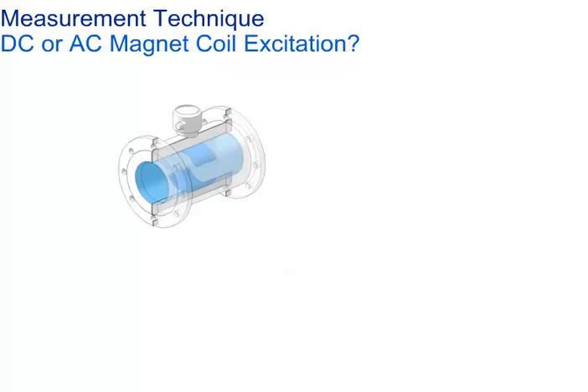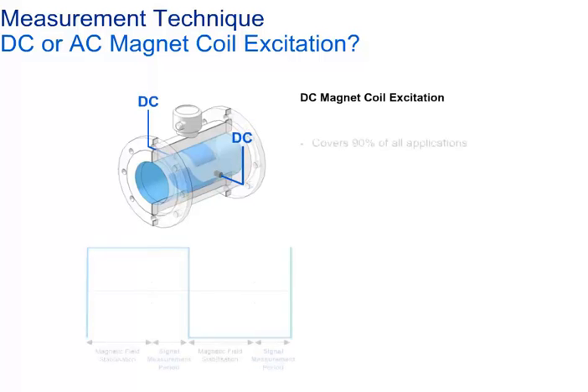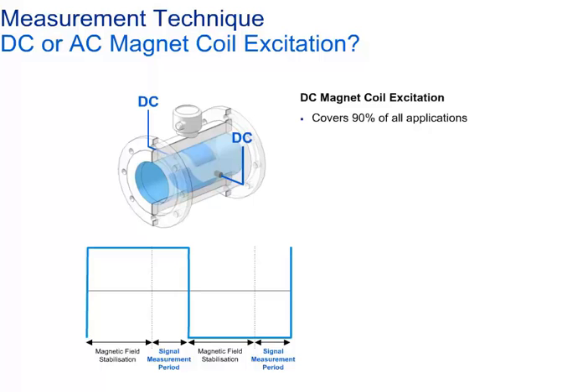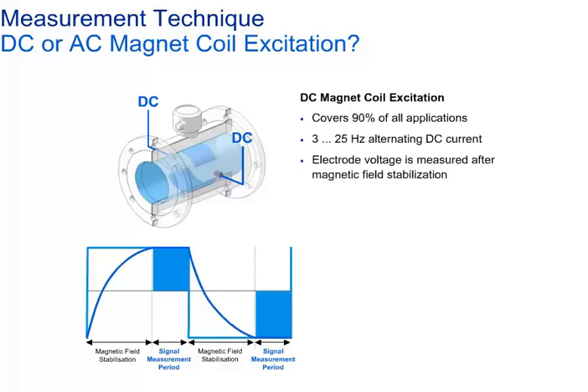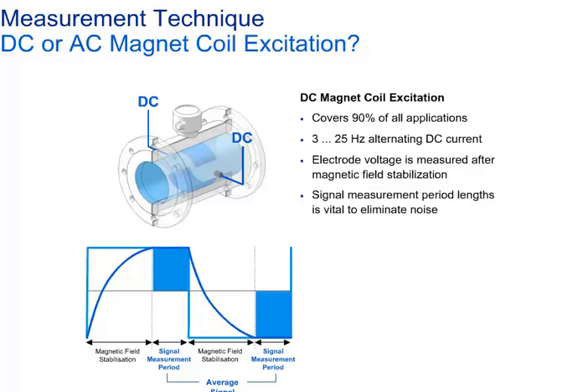There are two types of magnet coil excitation used. DC magnet coil excitation covers 90% of all applications, and AC magnet coil excitation. With DC magnet coil excitation, the coil is fed with a frequency of 3 to 25 Hz alternating DC current. After the magnetic field is stabilized, the sensor electrode voltage is measured. The signal voltages, positive and negative, are averaged to produce a flow signal. The electrode signal measurement period length is chosen specifically to eliminate noise from the AC mains line voltage.